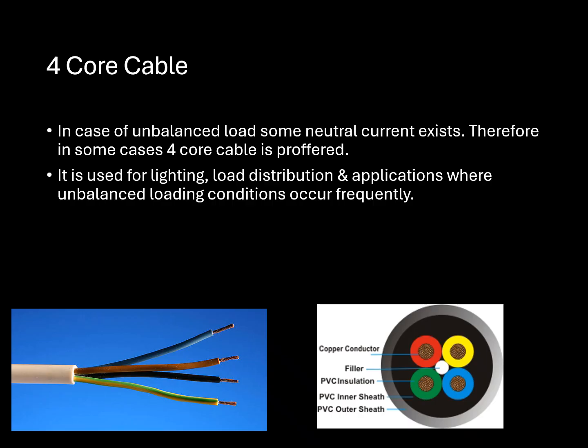Four core cables are used in very much unbalanced load, so the neutral carries more current and therefore it is made of equal size. So there will be four different equal portions, three carrying the three different phases, and the green one carries the neutral, this one.